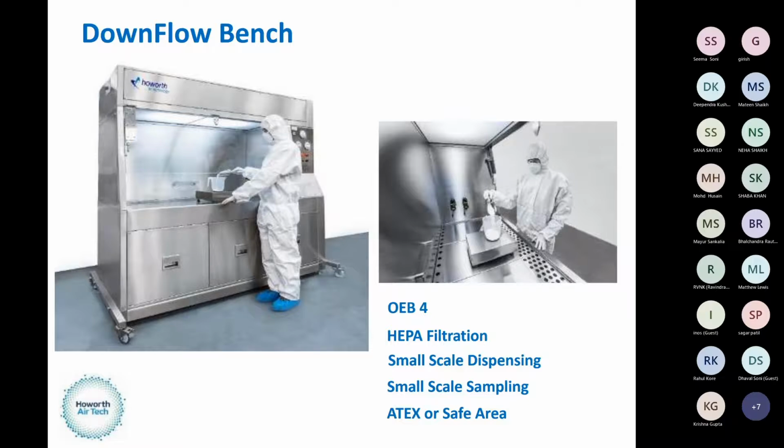We've just tested this system. We've done an independent containment test, and we were getting figures way below 1 microgram. But we have to be cautious because this has not been designed for a high containment system.